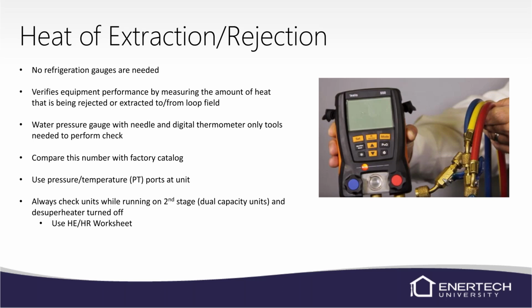Again, if you don't have them, you call in. The only way to really establish flow is to drain the water leaving the unit into a 5-gallon bucket and time it to see how long it takes to fill it up. So that's why pressure temperature ports are super important.